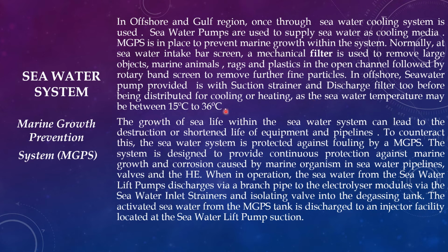The seawater temperature may be between 15 and 36 degrees centigrade. Either it is used as cooling media in a heat exchanger or cooler, or as heating media in an LNG regasification plant. In the LNG regasification plant on the offshore platform, seawater is used as a one-time heating media to regasify the LNG, which is at minus 163 degrees centigrade. So it is gasified by using the seawater only.